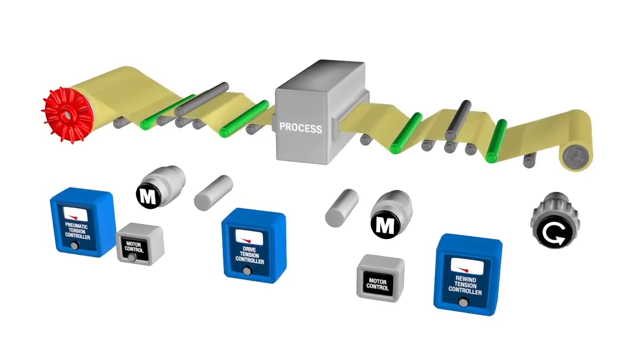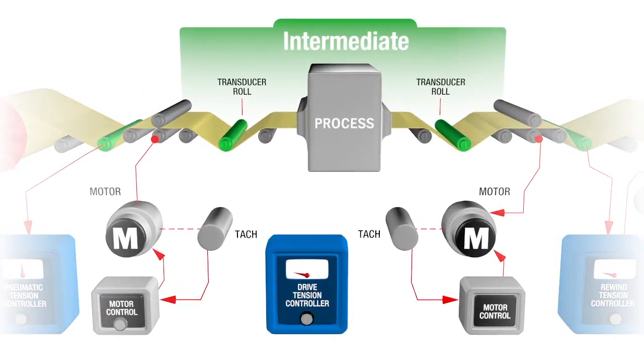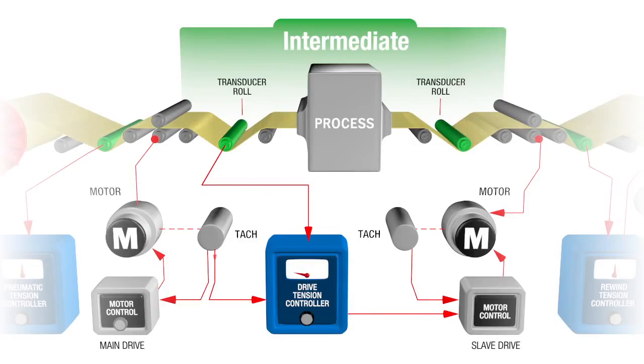A web process may involve one or more intermediate zones. This can occur prior to the main drive station, or after, or both. In this zone, the transducer signal is used only to trim the line speed signal as a follower of the main drive speed signal. This is usually at 5 to 10% of the maximum controller output.